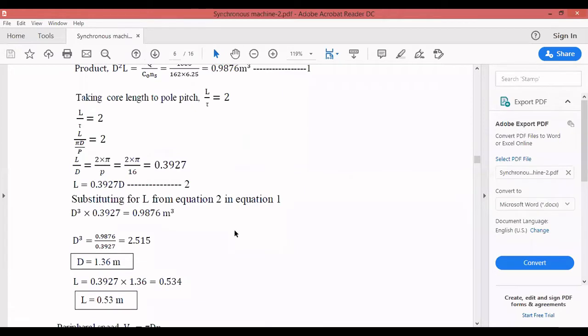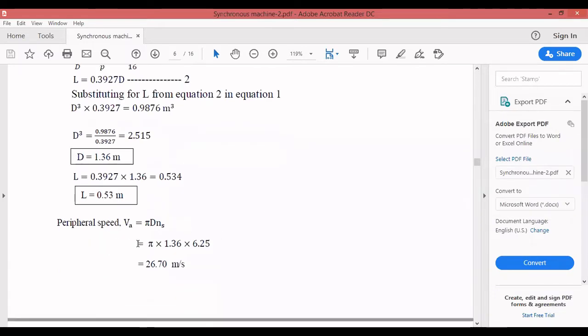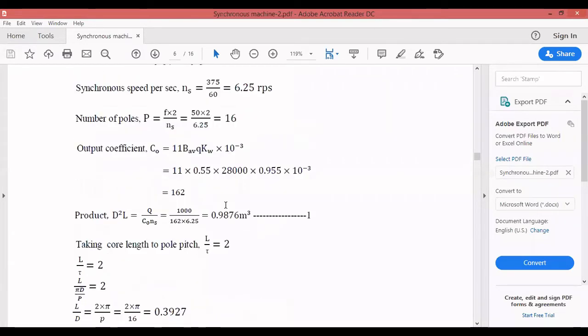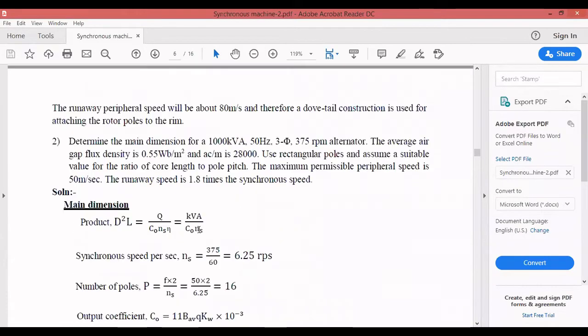With L/τ = 2, we calculate D = 1.36 m and L = 0.53 m. Then we check the peripheral speed: v = π × D × ns = π × 1.36 × 6.25 ≈ 26.70 m/s. This speed is within the limit of 50 m/s.